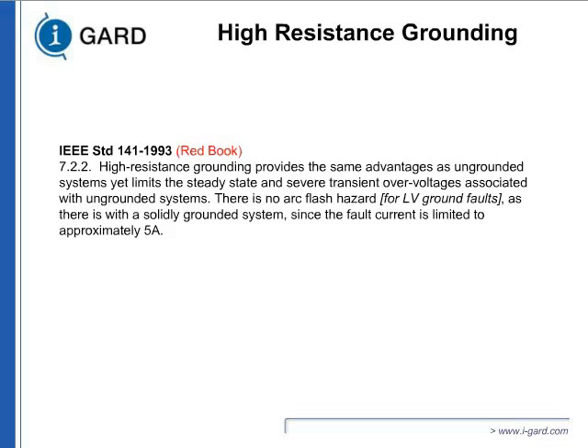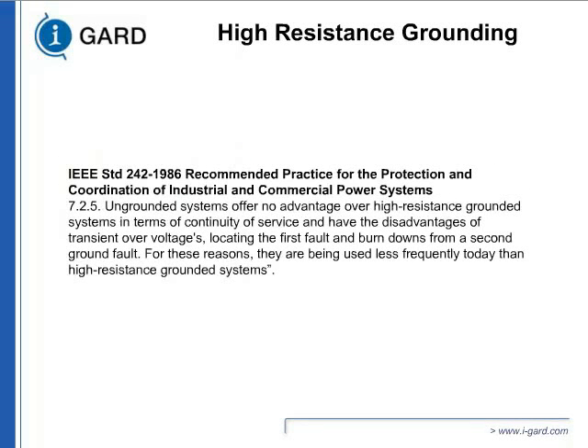This is again Buff Book, 1986. Ungrounded systems offer no advantage. So if you have that, it's very easy to convert. It has no effect on the process, as opposed to a solidly grounded system. You can very easily convert it and get the advantages: control the transient overvoltages, detect the first fault if you can, and minimize the equipment damage.